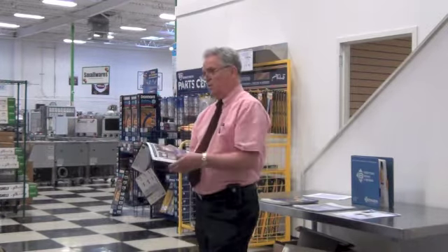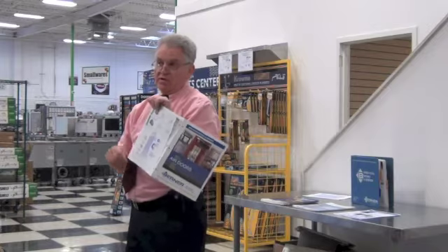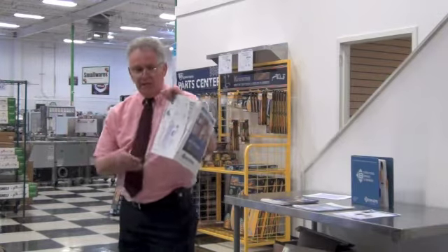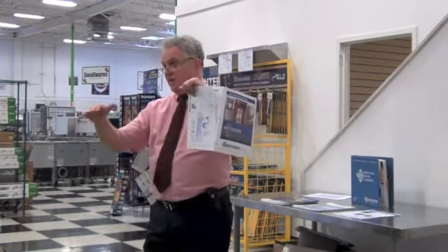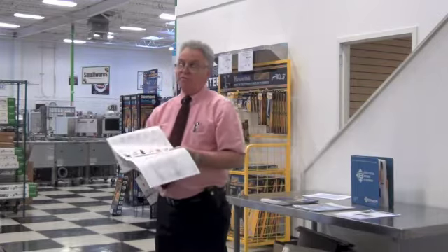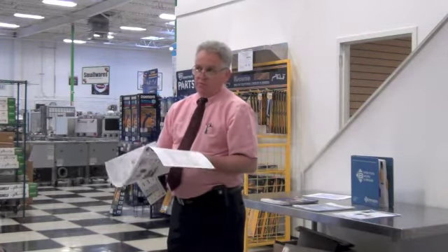If you're environmental, you want to put it on the inside. And why do you want to do that? When you're on the outside of the door, the air's coming down and it's mostly coming to the outside, and that's helping to keep your flies out of the building. When you're doing conditioned air, you want to keep your heat in or your air conditioning in. That air needs to stay to the inside, otherwise it's drawing the warm air from outside into the building. You don't want to mix that hot air or cold air from outside and pull it into your environment inside. It will save the customer dollars by keeping the air conditioning or the heat in his building.